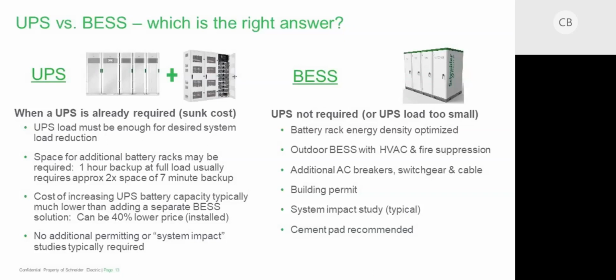But the way we have the control software set up, oftentimes you have excess battery capacity. If you operate a 2N UPS system, most UPS systems are going to be 50% loaded. If you designed it to have 10 minutes of battery runtime, you actually have 20 minutes if they're both 50% loaded. So you've already got the cost of the UPS, you've already got this investment in the batteries, and you have excess capacity. If you're lightly loaded, you may even have more than 20 minutes of battery runtime. And the way the software works is it will allow you to use the excess capacity on those UPS batteries, but it will never drain them below your minimum required runtime.